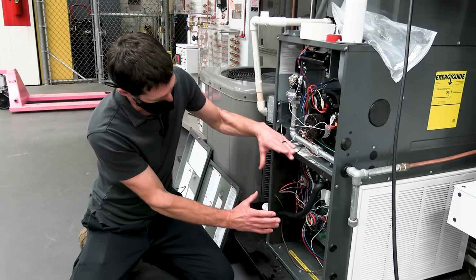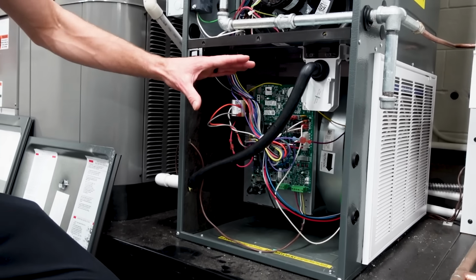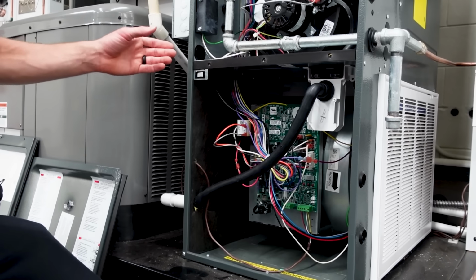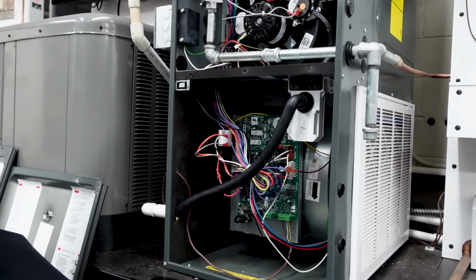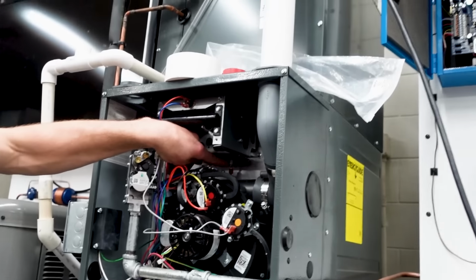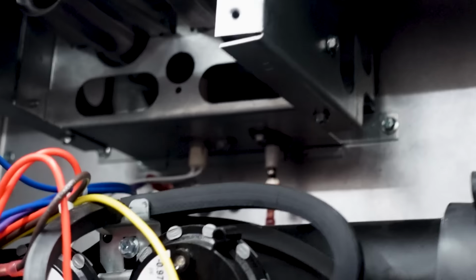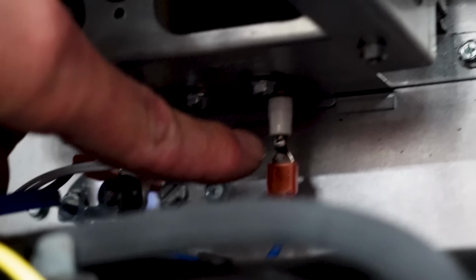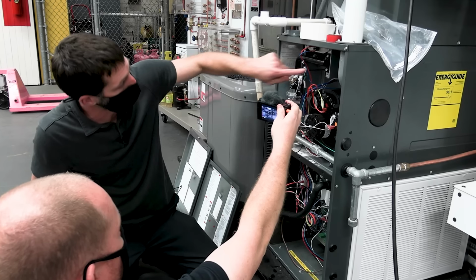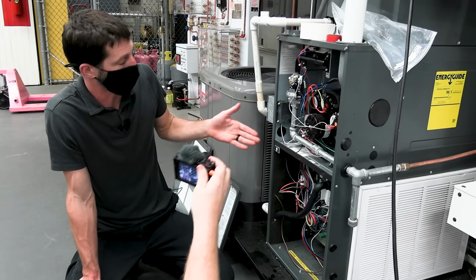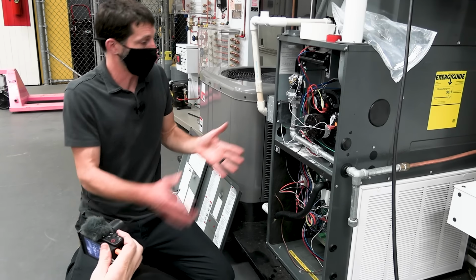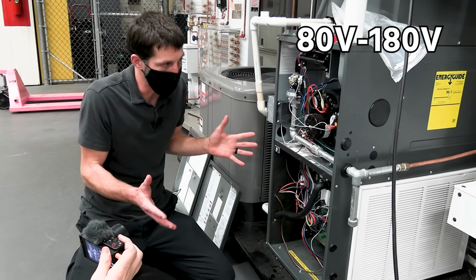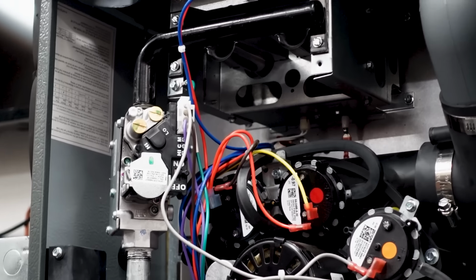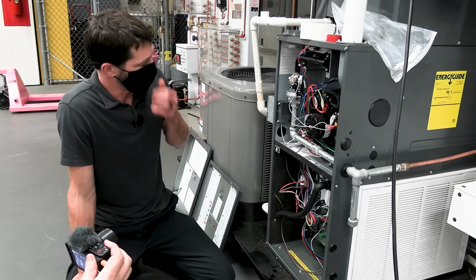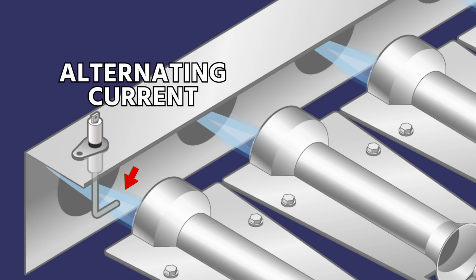This board uses flame rectification. At any time when you turn the power on, there's a flame rod right back here. That should be live anytime the furnace is on, which means that if you put a probe on this tab right here, which goes to the flame rod, and you put one on ground or common, you should be reading anywhere from say 80 to 180 volts. A lot of times with these gas furnaces, it's right around 100 volts. And that's alternating current. So basically you have alternating current ready at the end of that rod.